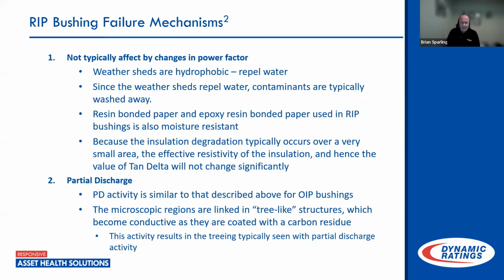Excuse me. Now that's the OIP type. The RIP type, because it's a solid insulated bushing, has no oil inside it. So the insulation system is completely different. The weather sheds on the outside are hydrophobic, so they repel water, whereas if it's porcelain and becomes contaminated, it has the propensity to keep water on the surface of the porcelain itself. So resin bonded paper, actually epoxy resin bonded paper used in RIP, is more resistant to moisture.